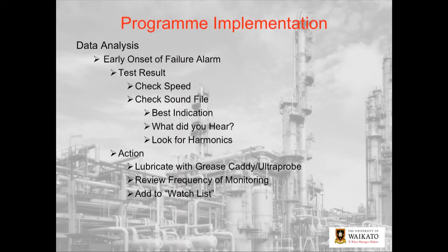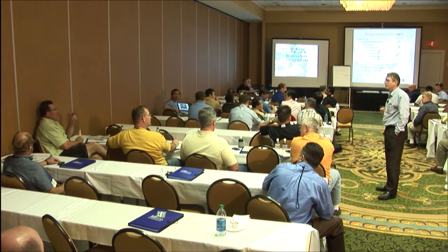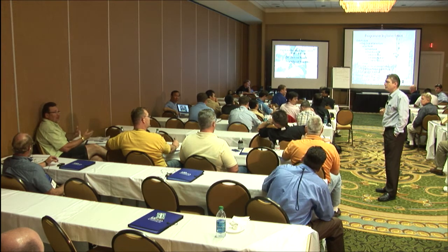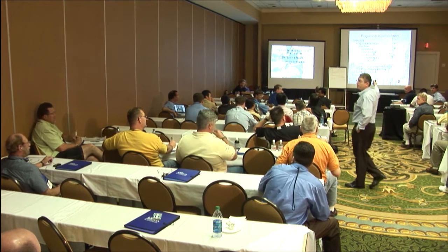Okay, let's talk now for a minute about a point that we struggle with quite a bit. We work with a lot of grain elevators. Grain elevators, yes. And instead of variable speed drives, it's loading and unloading of conveyors and belts. And it has exactly the same characteristics as a variable speed drive, so your load's changing. You have to establish different criteria for the load that they have that day, whether it's running empty, just to get the test, or fully loaded, carrying the weight of the grain that they happen to be moving. So yeah, you could apply the same principles the same way.